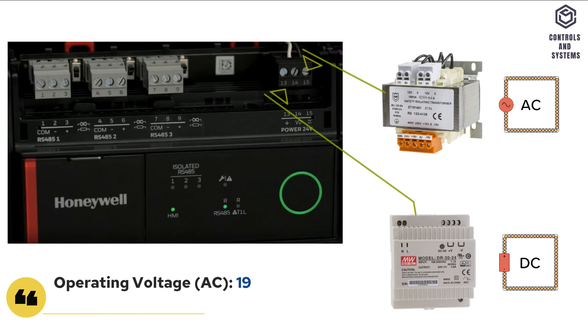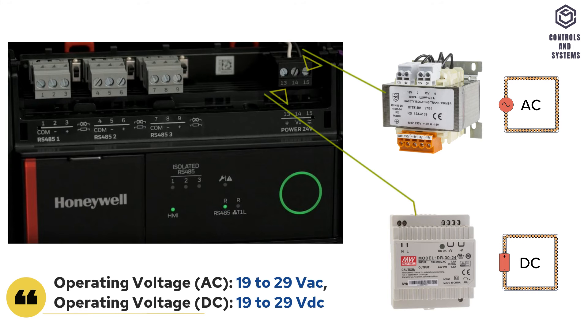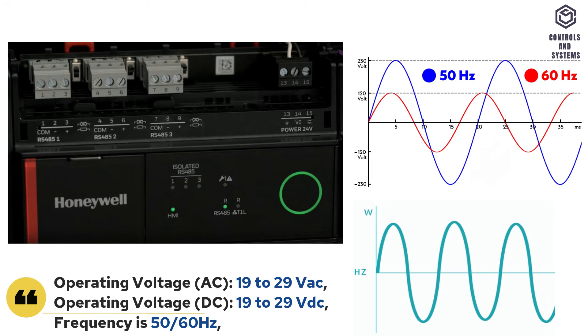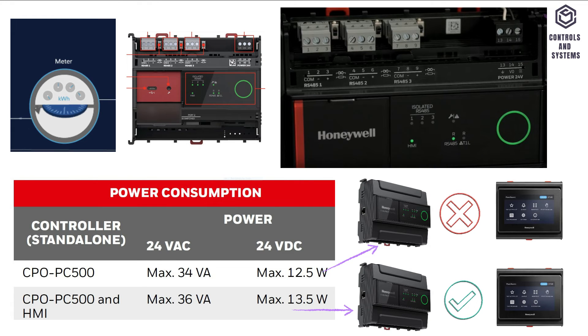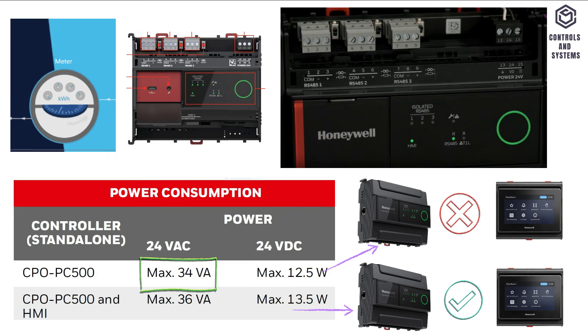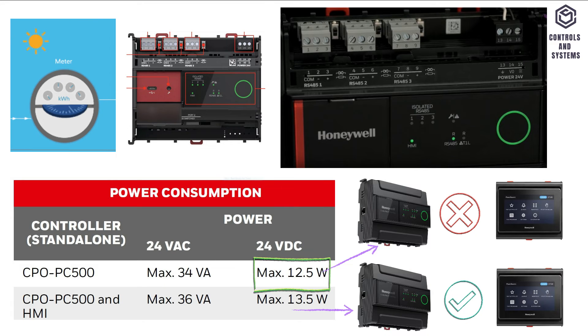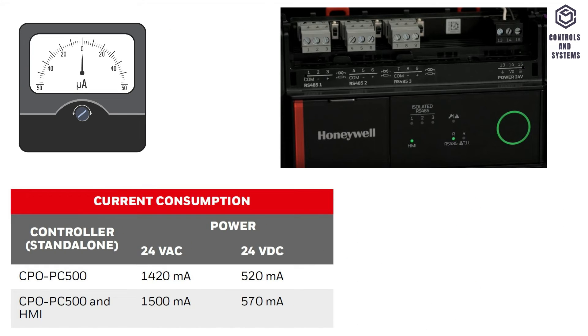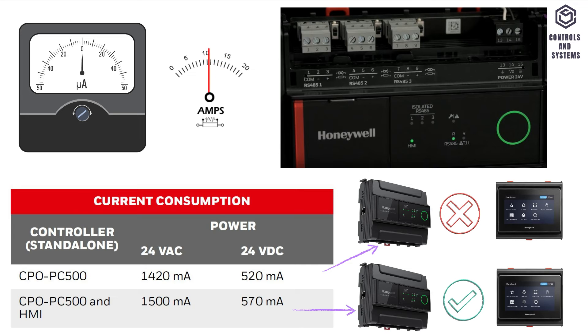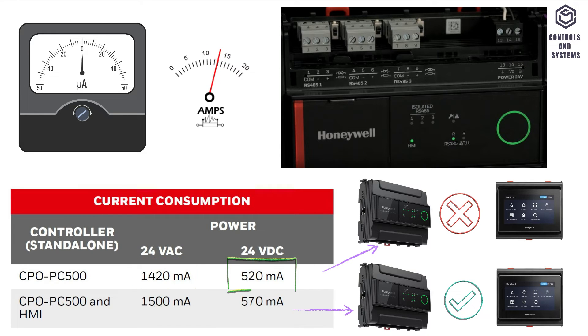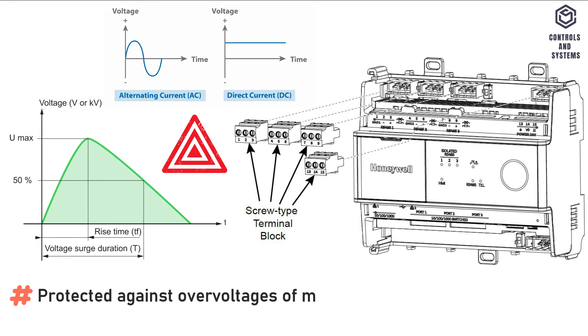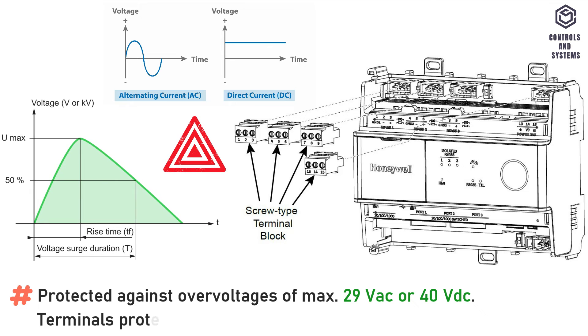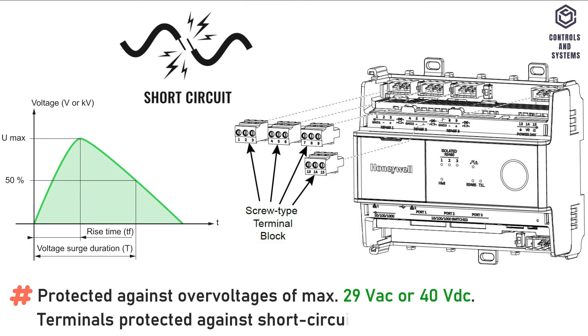Electrical Data: Operating voltage is 19–29 Volt AC or DC, frequency is 50 or 60 Hz. Power consumption for controller without HMI: maximum 34 VA in AC, maximum 12.5 Watt in DC. Current consumption for controller without HMI in DC is 520 mA. Protected against over-voltages of maximum 29 Volt AC or 40 Volt DC, and terminals are protected against short-circuiting.